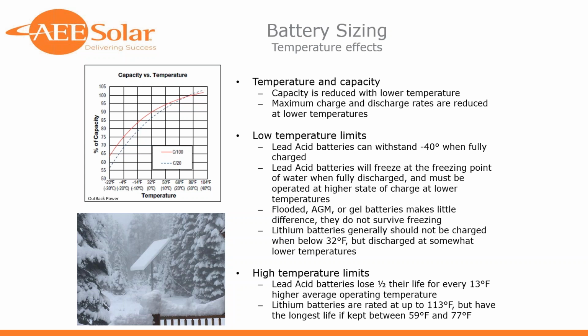So that's if you keep the battery fairly charged, the lead battery will go way down, minus 40 degrees if it's fully charged. It's just a matter of designing the system so that you don't ever discharge the battery too far if it's going to be really, really cold. But a lead battery tends to have so little capacity when you get too cold that the system stops working anyway.